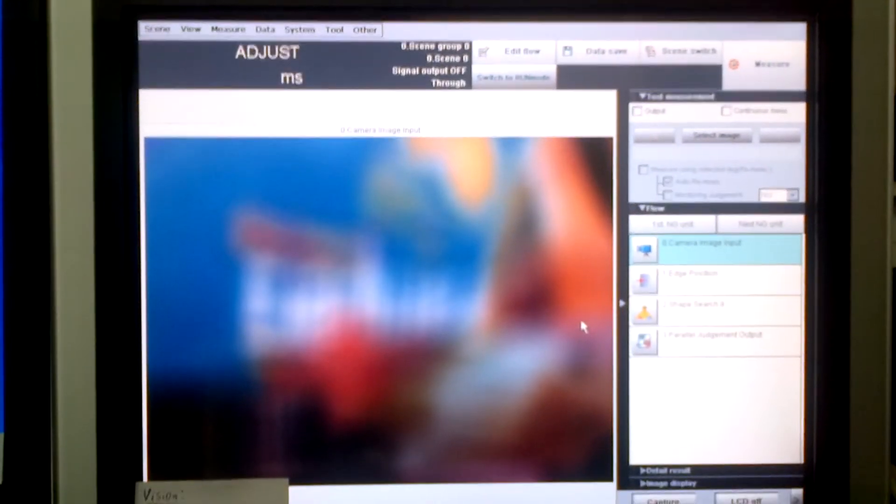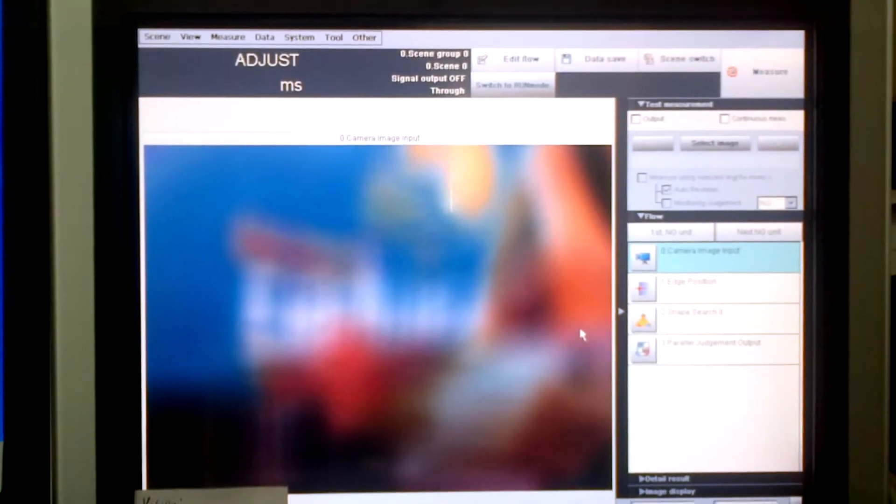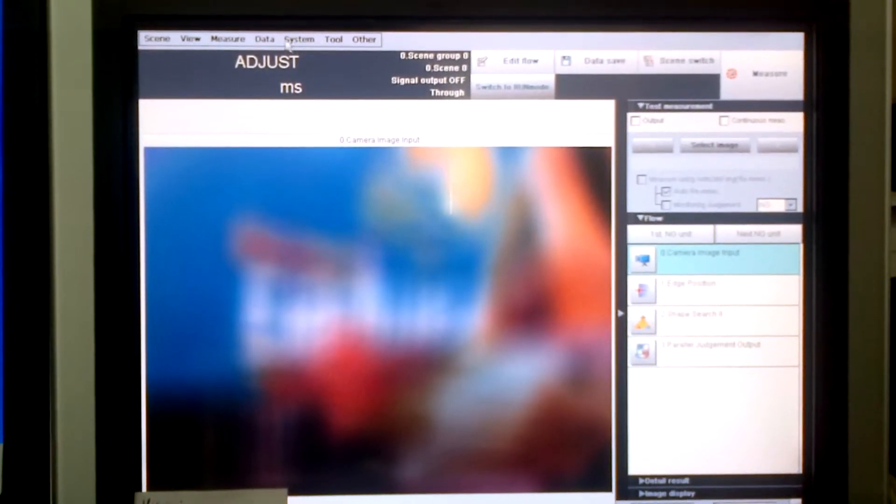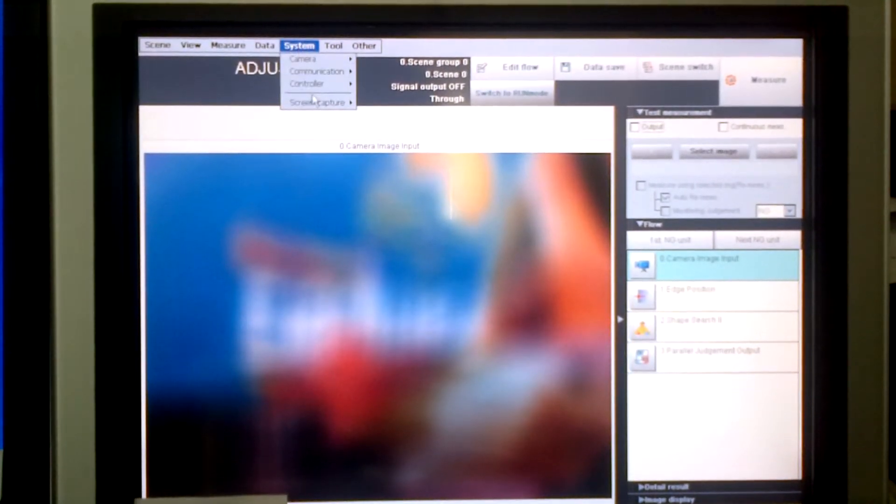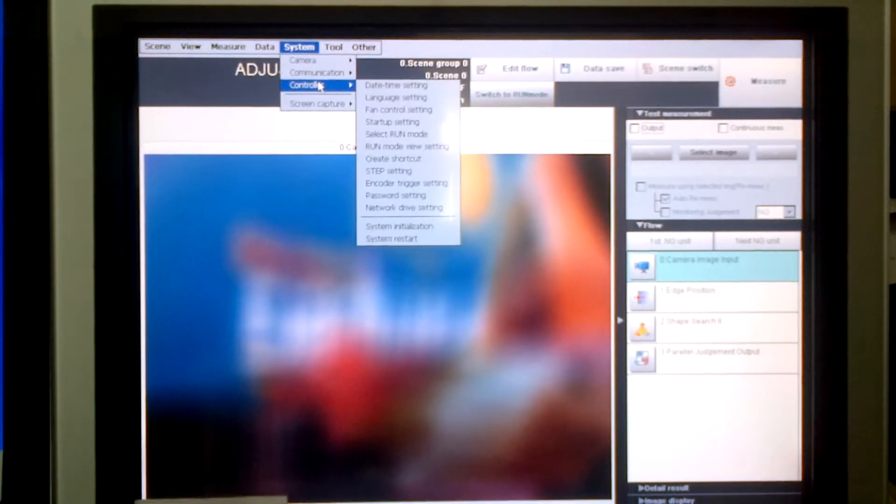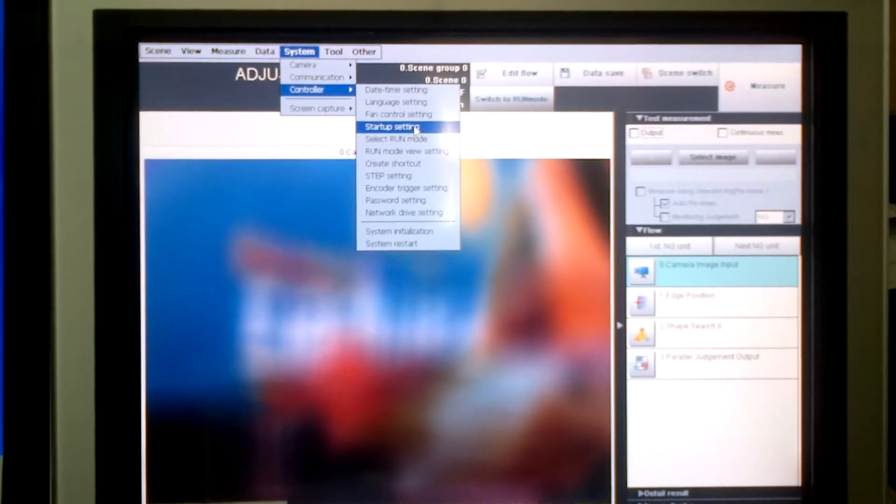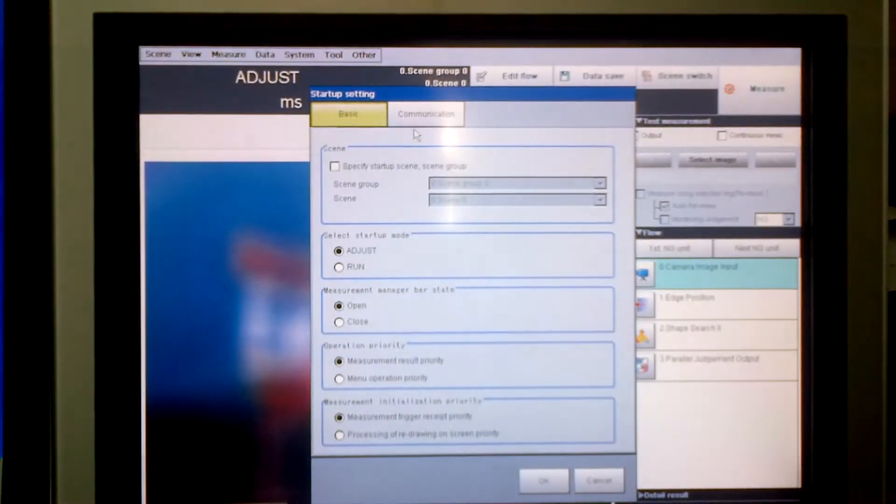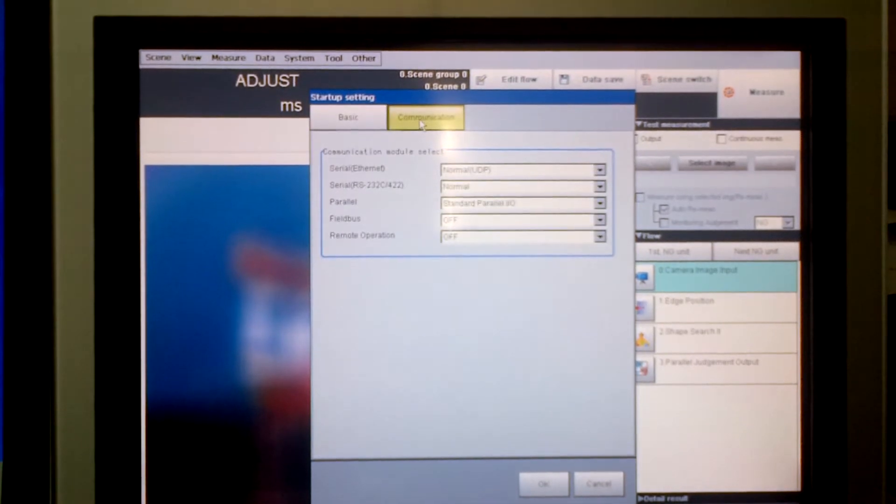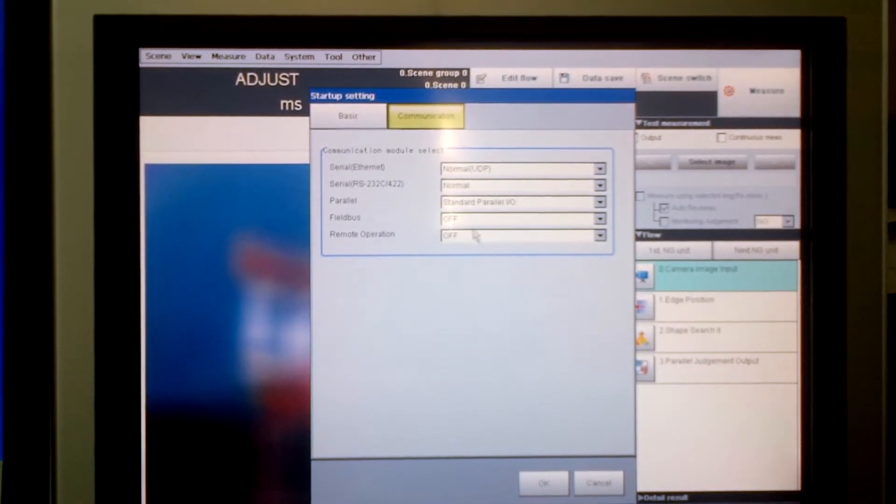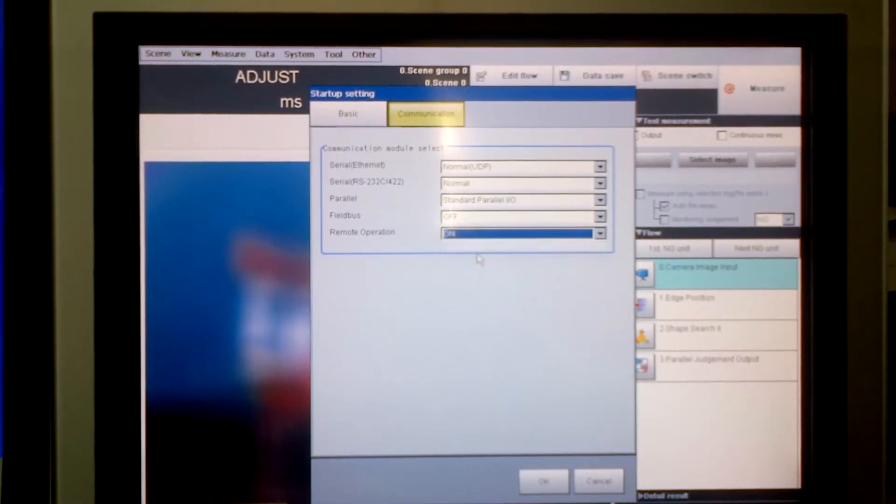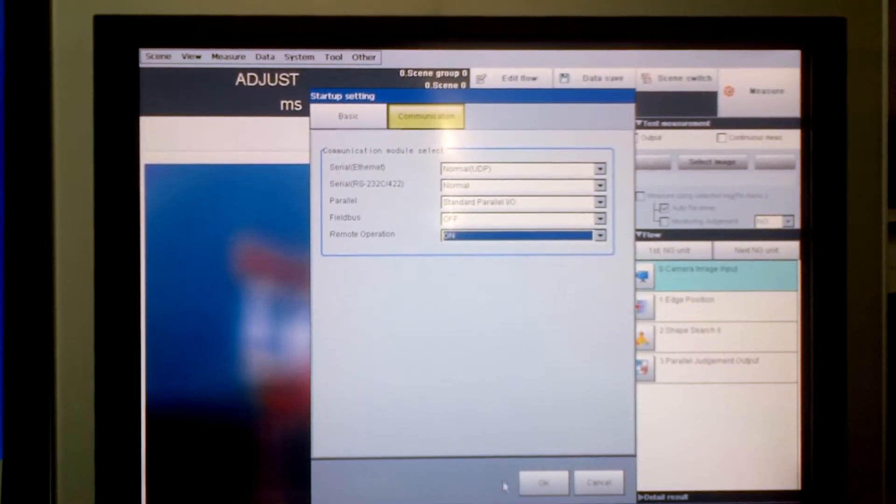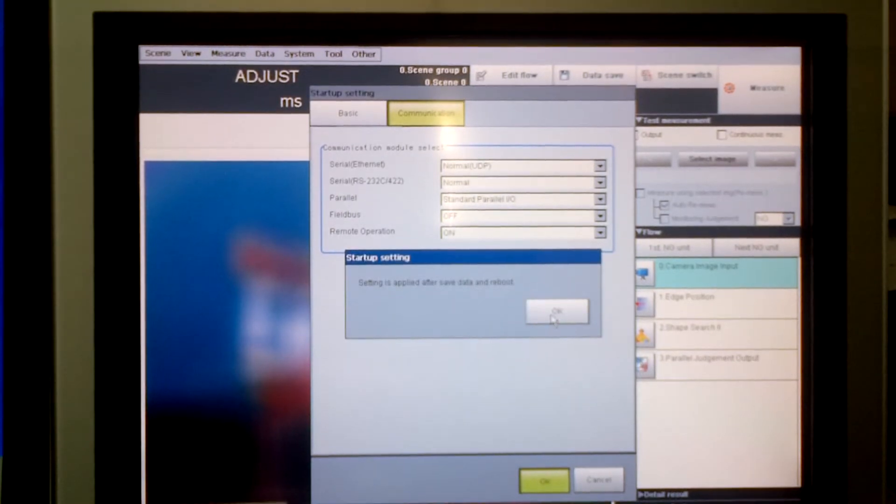The first step to setting this up would be to activate the remote operation on the FZ controller. So we go to System, Controller, Startup setting. Select the Communication tab. Turn on the remote operation. Select OK.